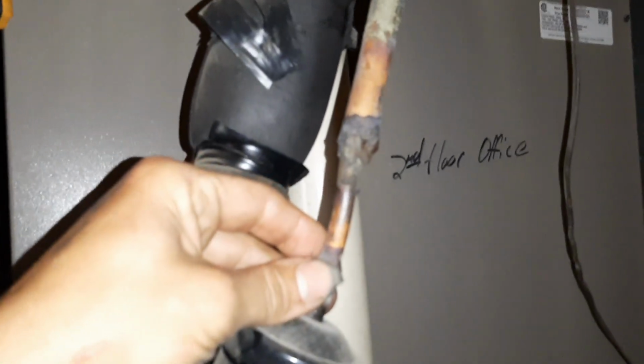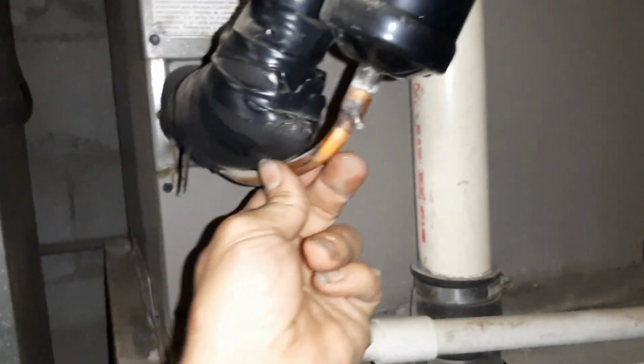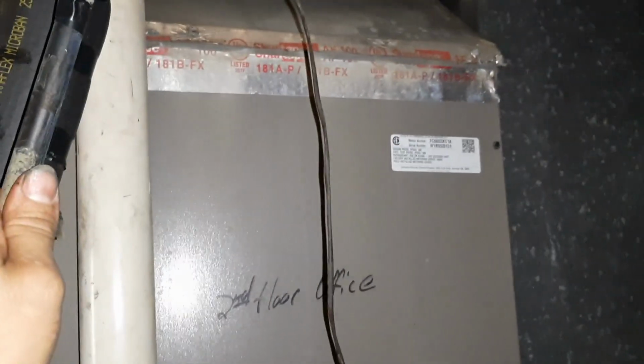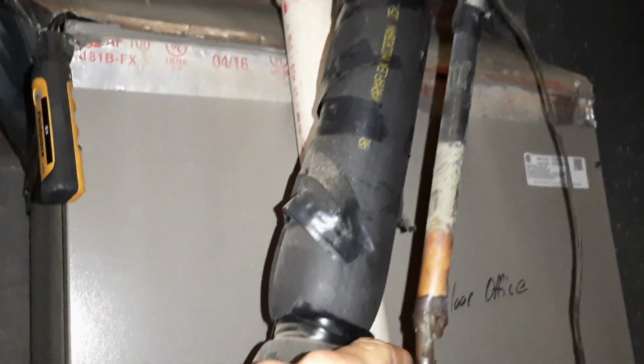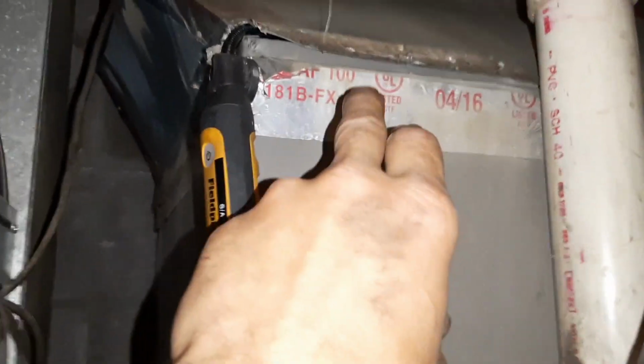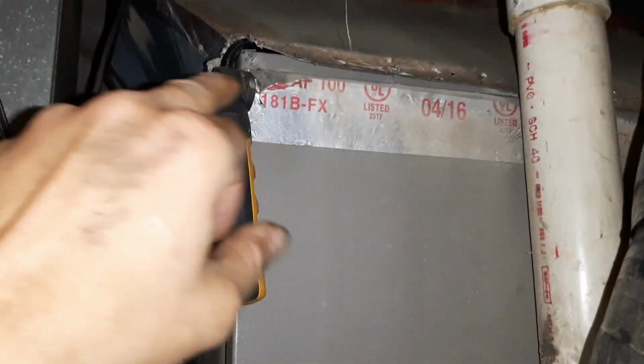So none of this is gonna be perfect. You can see what they've done with the liquid line there. The liquid line's pretty cold right now. Still got a wet coil too, I believe. I got a gap here. Nothing was ever sealed. They just shoved this thing in place. It says no metering device installed. So they would have had to have put it in there.